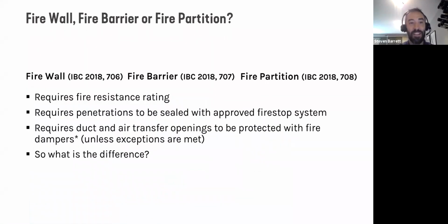So if we look at the next slide here, given the sections you can find in the International Building Code, IBC, firewalls are in 706, 707 for fire barrier, and 708 fire partition. All these require a fire resistance rating. All of them require penetrations to be sealed with an approved fire stop system. All require duct and air transfer openings to be protected with fire dampers, unless exceptions are met, which we'll get into. So what's the difference between all these?